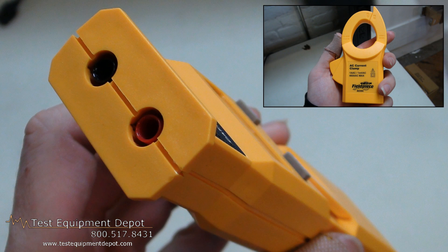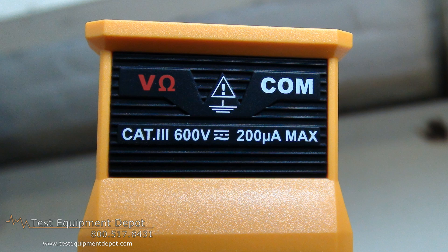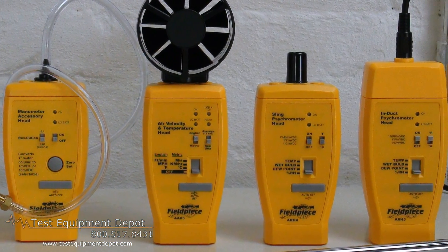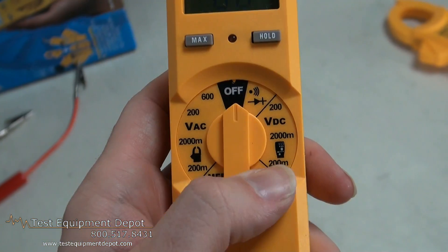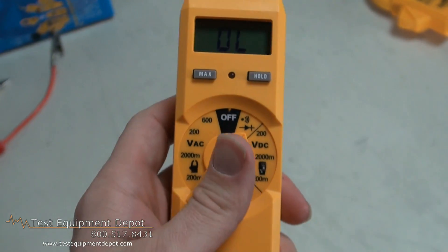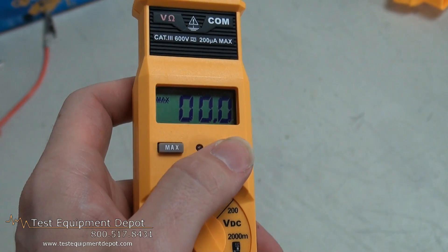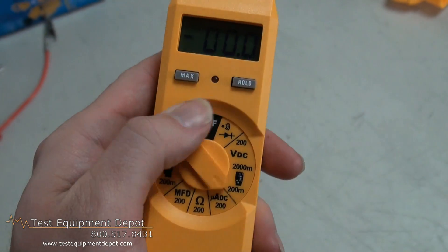You can use this to test motor run and start capacitors. It has 0.1 ohm resolution for ohming out a motor. It works with all Fieldpiece accessory heads, and it has modular expandability and will also read microamps DC for flame diodes.